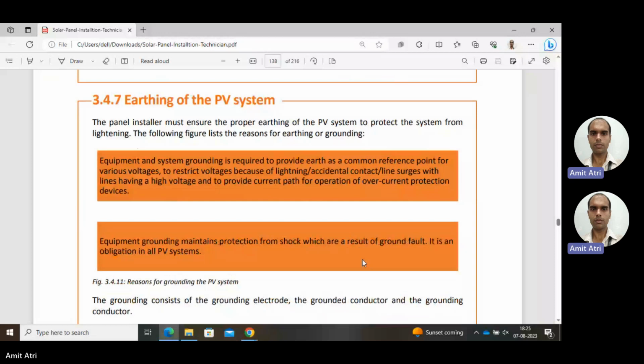So how could that kind of over voltage situation occur? In case of lightning, it could induce extra voltage, over voltage. Then in contact with other live lines, some surges may induce a high voltage in our PV system. Some type of overcurrent. These things can occur. So we have to provide an alternative path towards the ground so that this over voltage does not harm any component in our system, or our load as well.